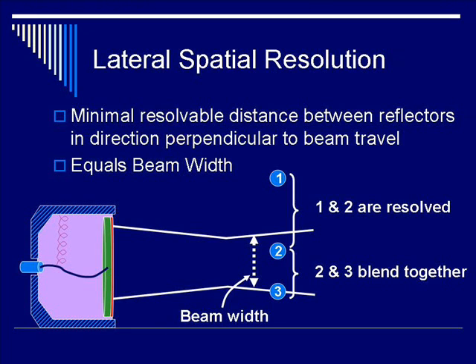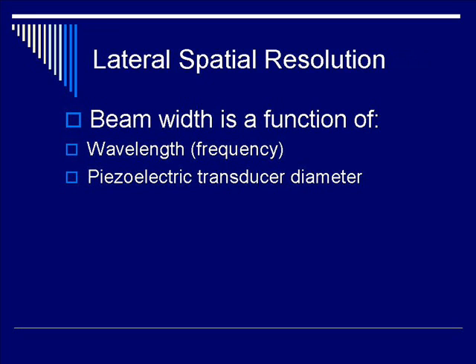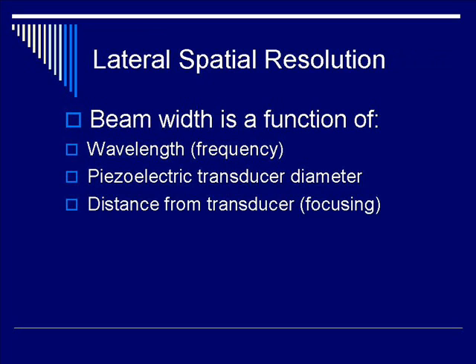On the other hand, particles 2 and 3 cannot be resolved and they blend together because they are both within the beam path. Beam width is a function of wavelength or frequency, first and foremost. It is also a function of the piezoelectric transducer diameter, which we will go into more detail later in this lecture. The third function is the distance from the transducer, which we will describe in more detail during the beam forming section.